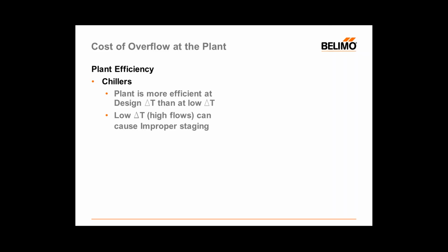Chillers are an interesting piece of equipment, and there's probably a ton of you on the call today that know a lot more about chillers than I do. But I think one of the things that we can say is that chiller plants are simply more efficient if they're operated at their design delta T than if they're not. And the reason I'm making such a generic and cryptic statement is that the impact of low delta T on a chiller is highly dependent on the chiller.